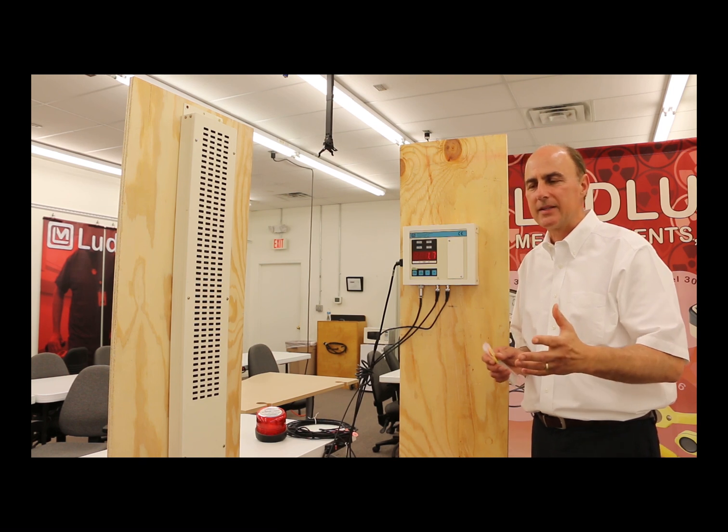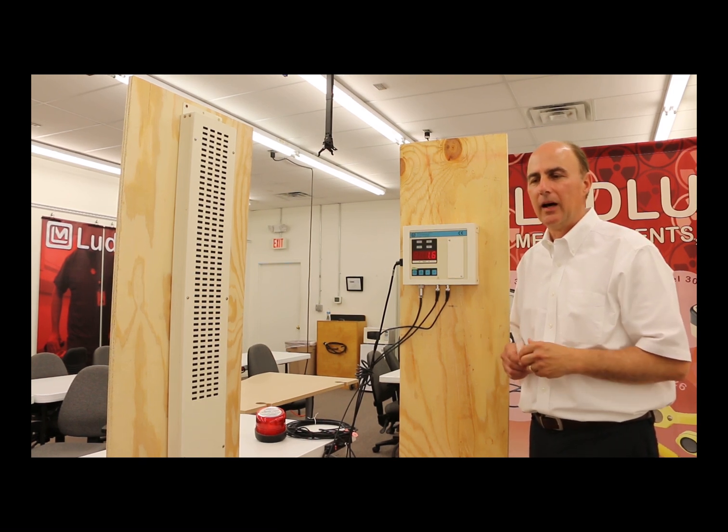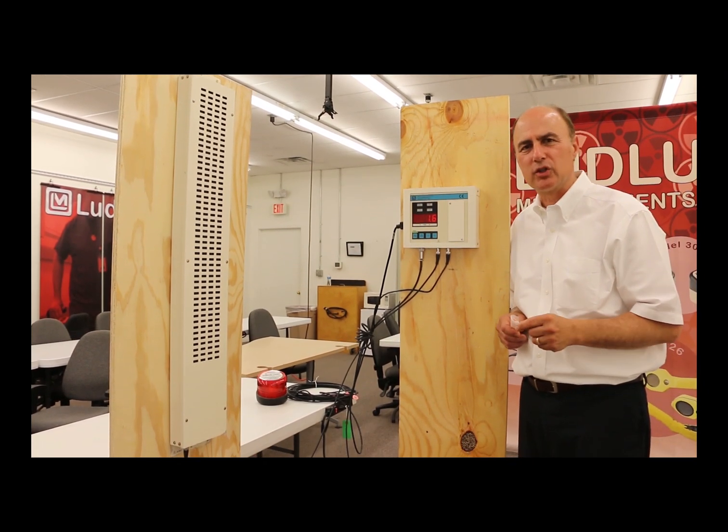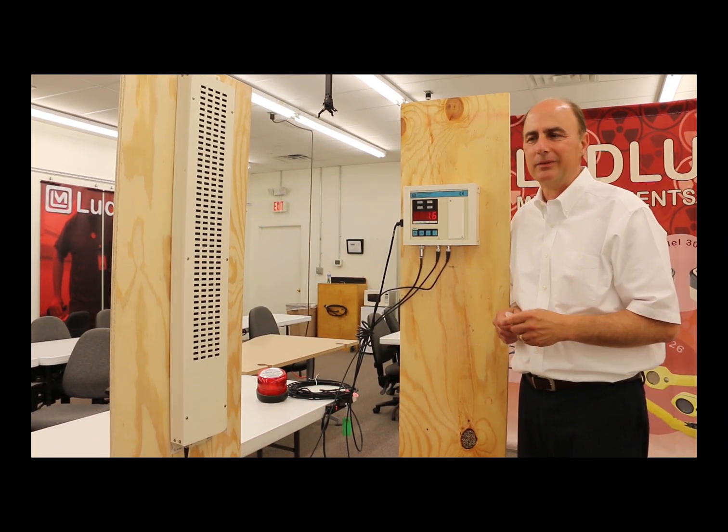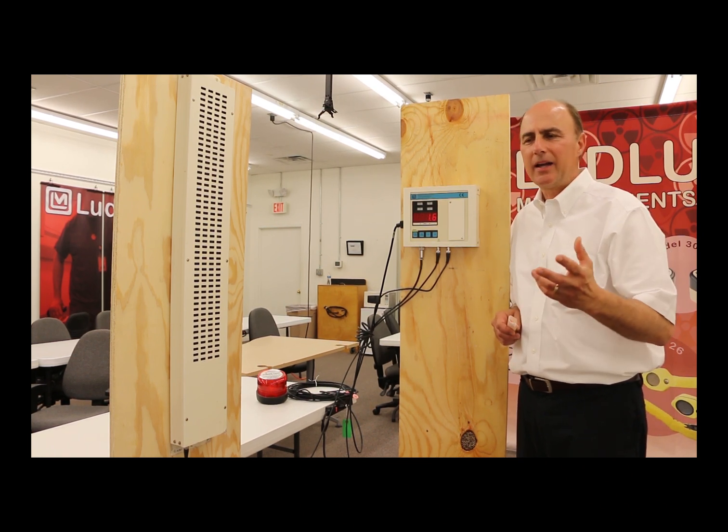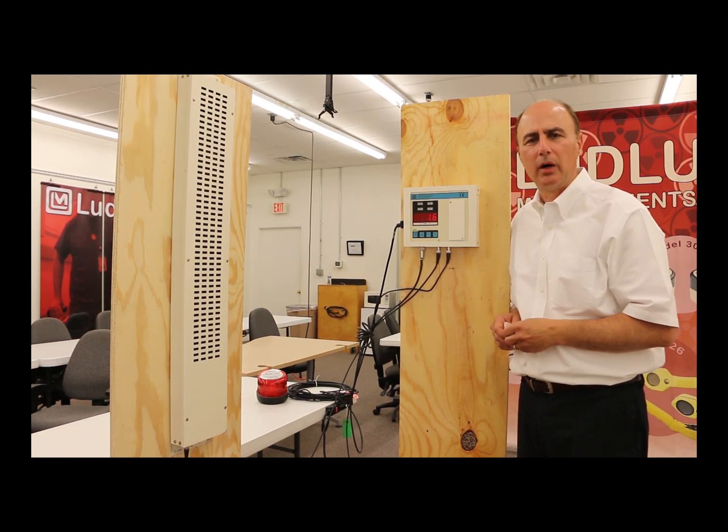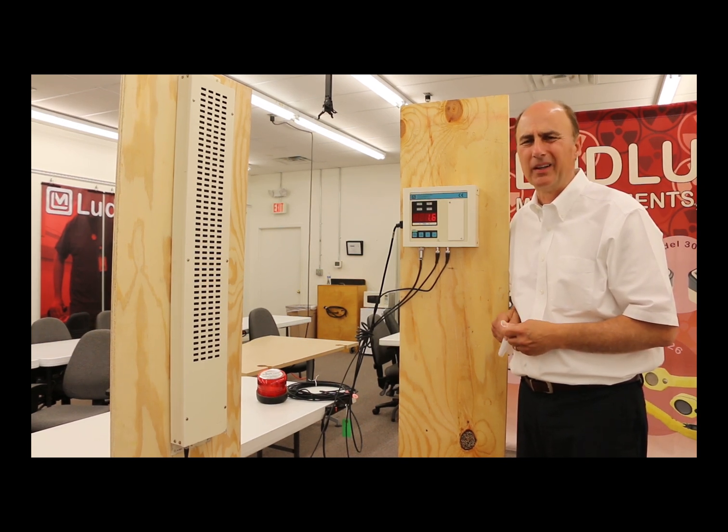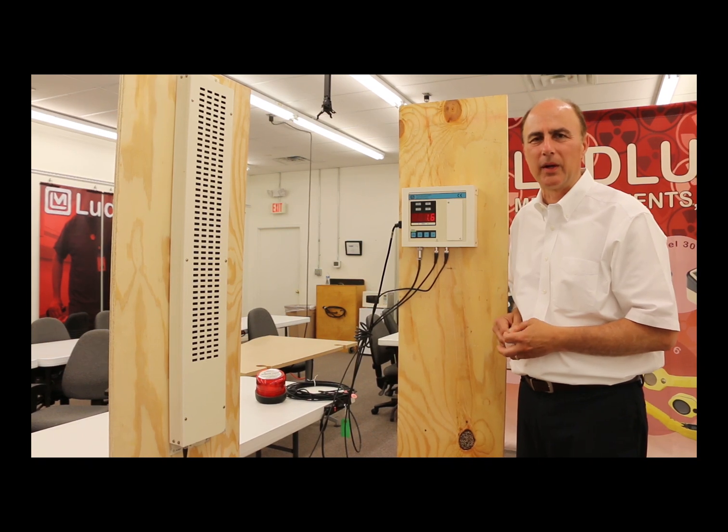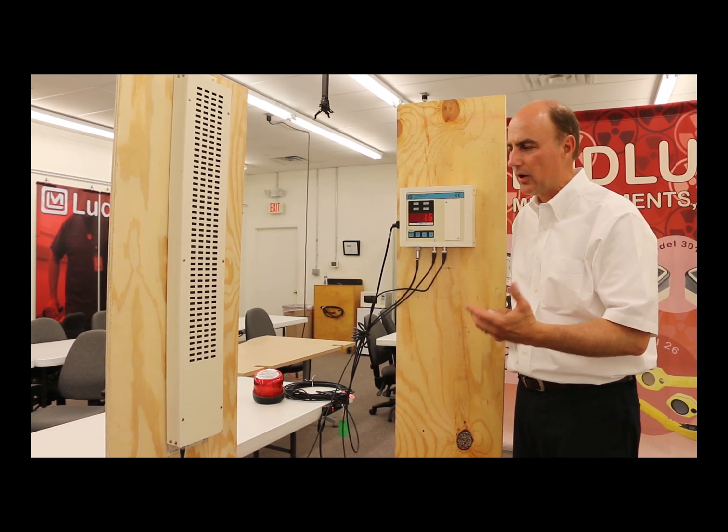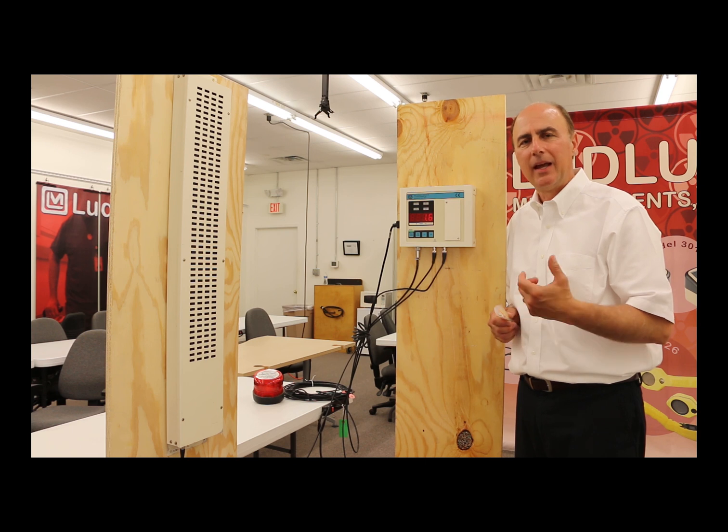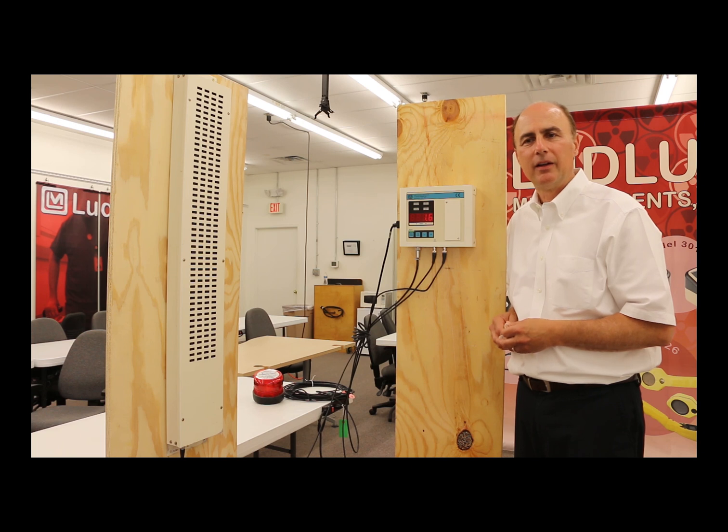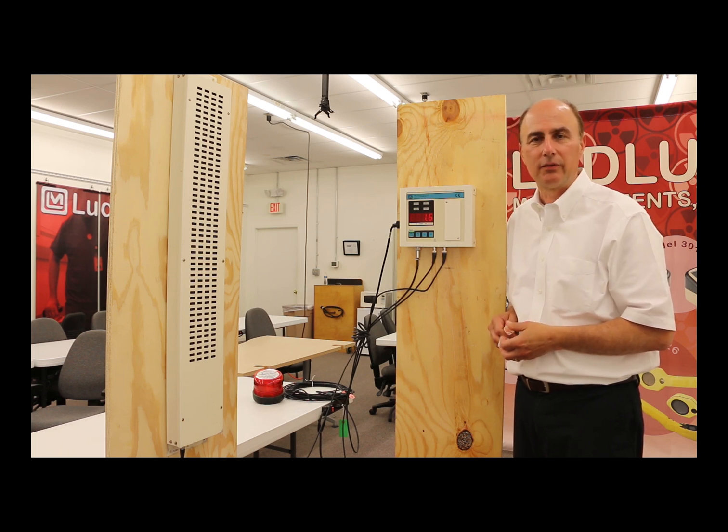Then they'll typically take those bags that are offending. If you're at a nuclear medicine facility, normally that's Tech 99 or something with a very short half-life, the six hours, things like that. You know that, hey, I can move that off into a shielded room or a room that's locked. And within a couple of days, really there's no detectable radioactivity in it. So typically folks who get the alarms, they identify the bag, and then move them and sequester those bags until they've decayed enough that they're safe to send off into municipal waste.